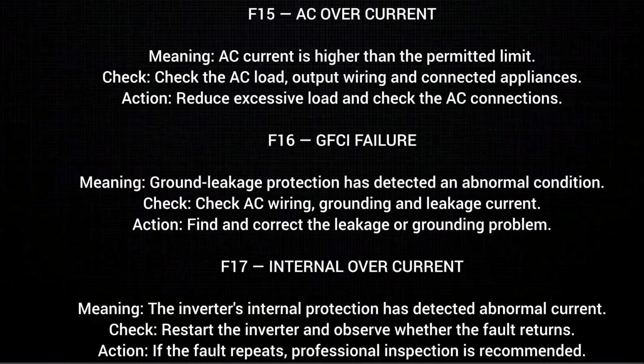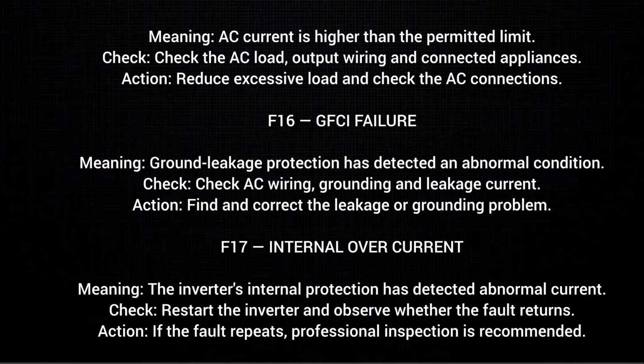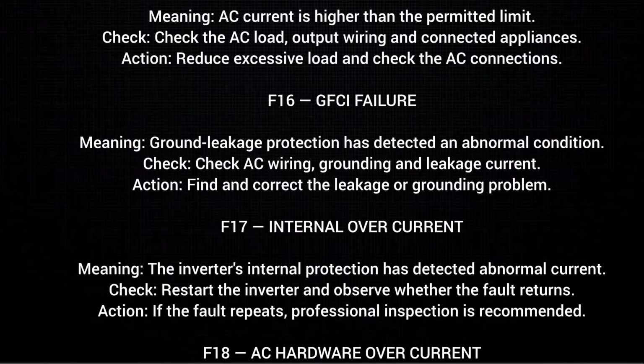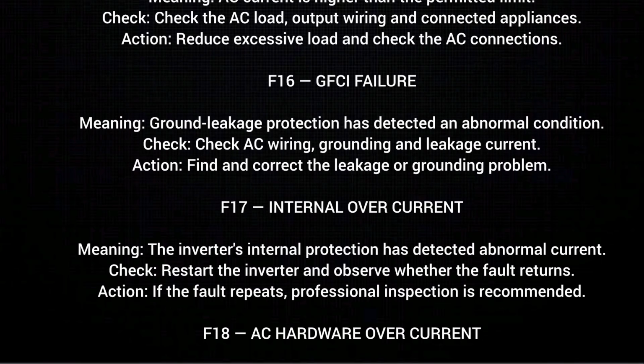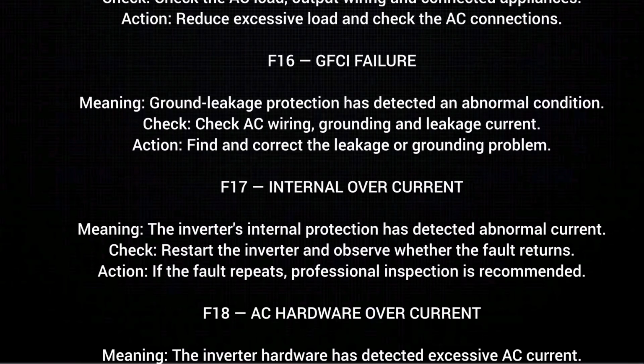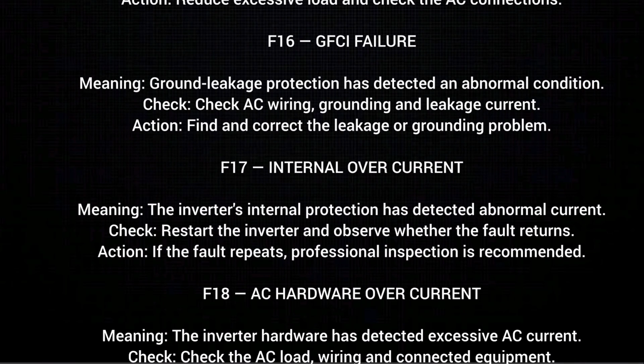F16 GFCI failure, meaning ground leakage protection has detected an abnormal condition. Check. Check AC wiring, grounding and leakage current. Action. Find and correct the leakage or grounding problem.